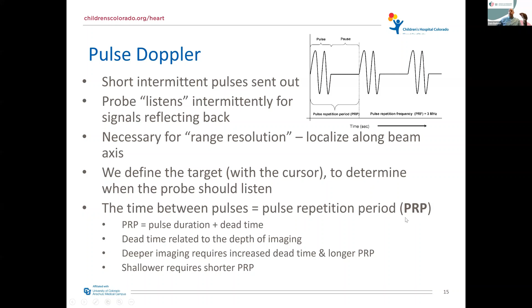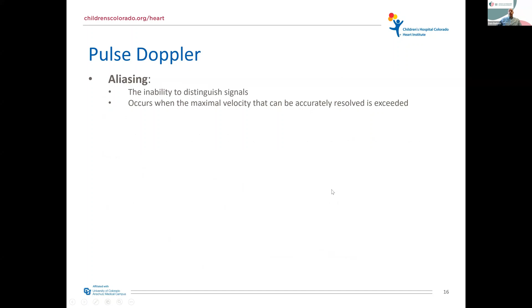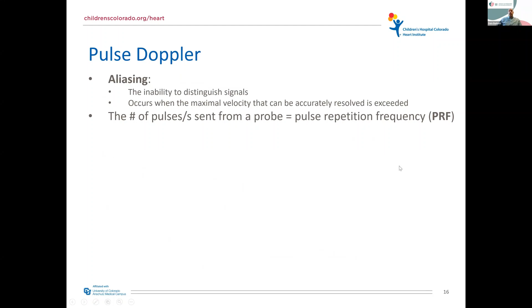So aliasing is an important concept. When we talk about aliasing, it's helpful to understand this. Aliasing is the inability to distinguish signals. So you can't accurately code a signal when it comes in. And this basically occurs when the velocity that you're trying to measure is too high for the machine to actually resolve. We'll show you an example of this on this screen in a second, but it's related to the PRP and the pulses that leave the probe.